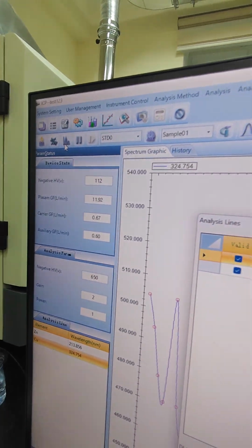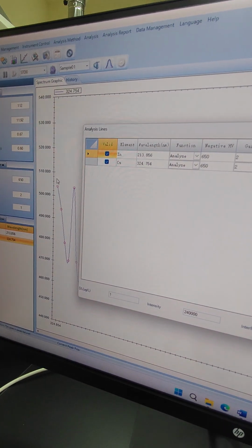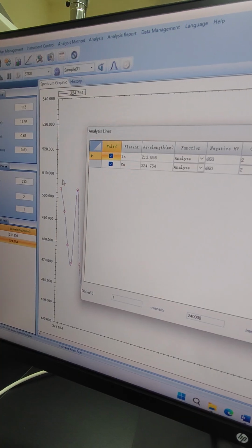For these peaks, usually we set the value. For example, it's around 4,000. If it's low, then we raise this value. If it's high, we lower it. Normally, we will change 20 or 30 every time. After the change, we go to do the search peak again and check the value. If it's still not reaching around 4,000, we will change here again.